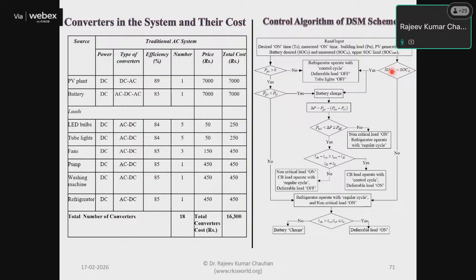This algorithm will compare the state of charge measured and the state of charge desired at a particular time instant. There may be a peak time of solar generation when load is also present, but the battery needs to be charged first before supplying other loads, because the critical load needs to be supplied when the sun is not available.